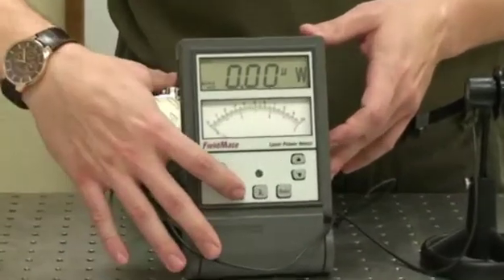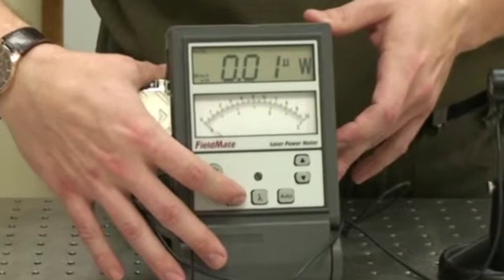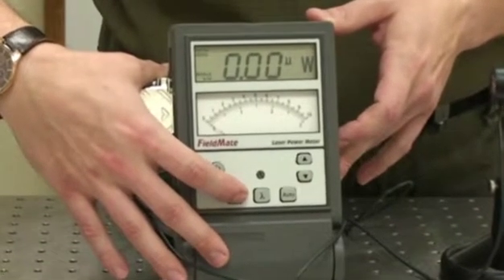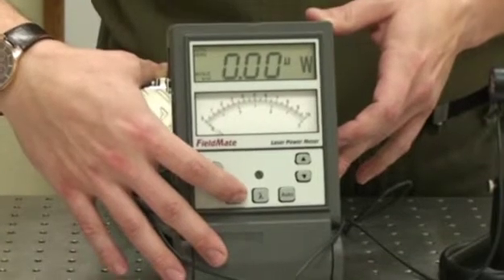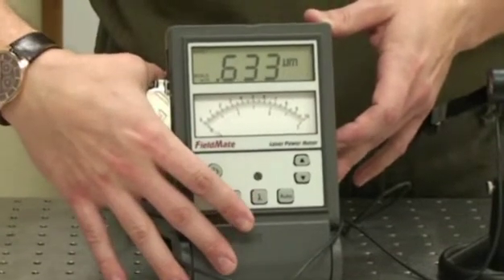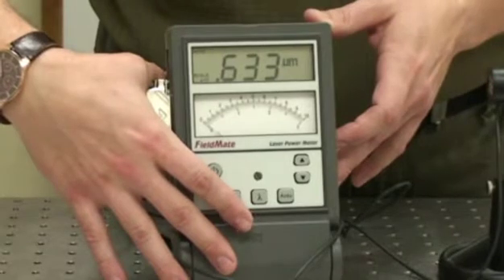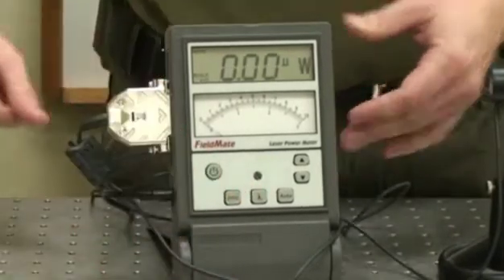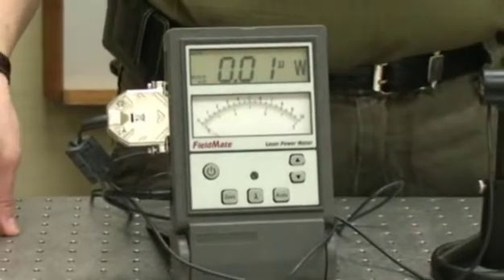And when it comes up, I'm going to hit the zero key to make sure we are zeroed. You'll see it start to zero. And we'll check our wavelength which should read at 633 nanometers. Now we should be ready to receive laser light.